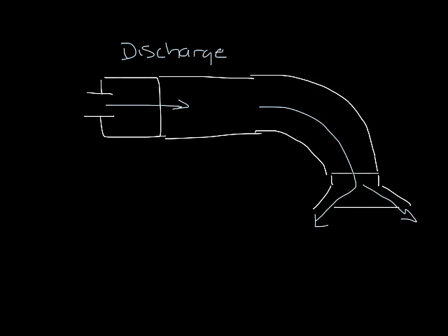So now let's look at discharge sound. Let's draw our single duct box again and duct it out to a diffuser. Discharge air flows through the box, down the ductwork, and then out the diffuser into the space. Ductwork is usually lined, and lined ductwork is an excellent attenuator of discharge sound from the box.